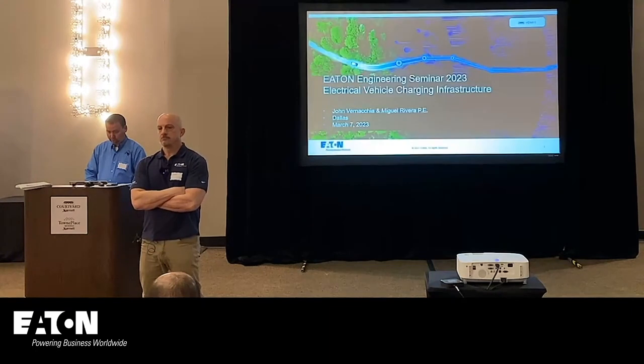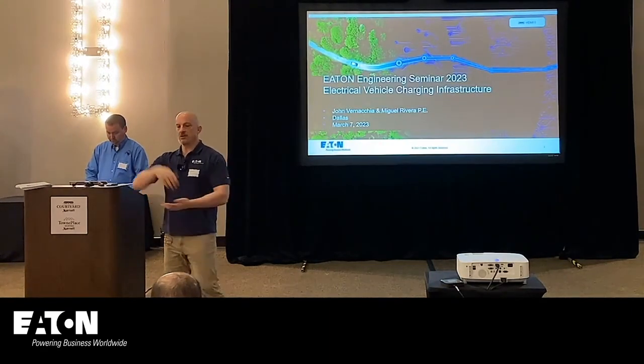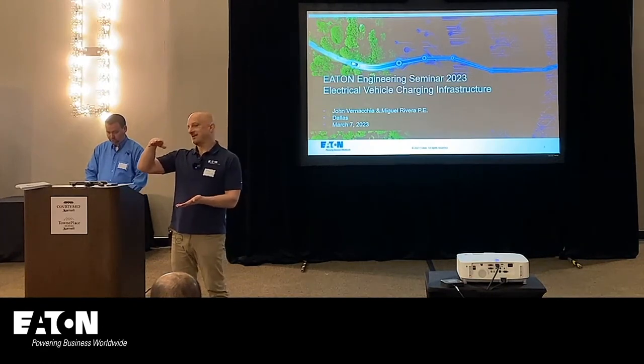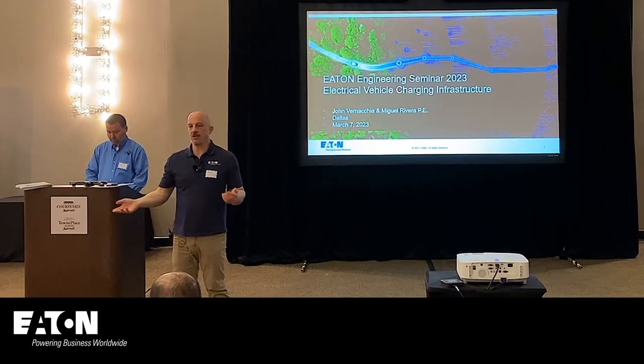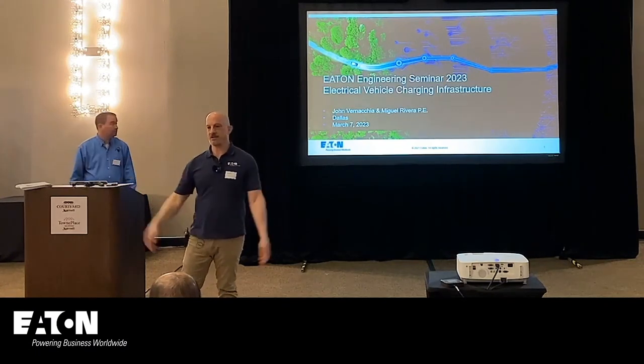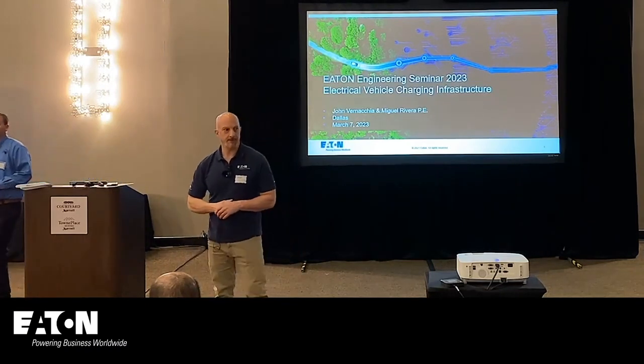Is Tesla much better? No, I mean, it would go from, say, 4% distortion. So on a 100 amp basis, they had 4 amps of harmonics, and the other ones had 8 amps. So if you look at the waveform and you didn't have a meter that could measure it, you would think they're the same. It's very close, very close.